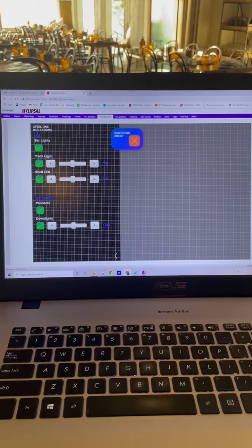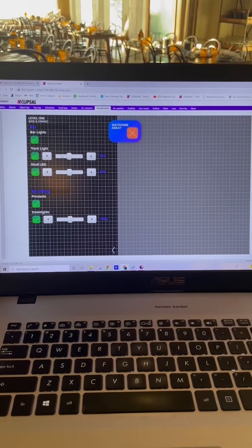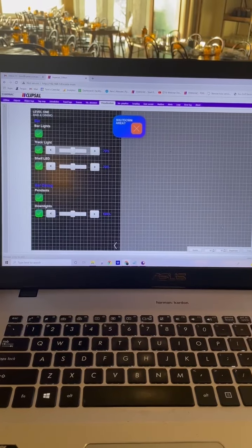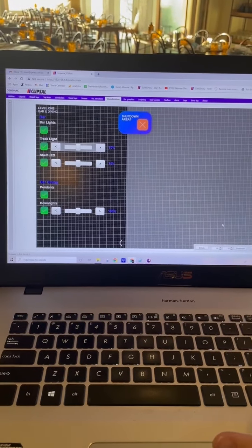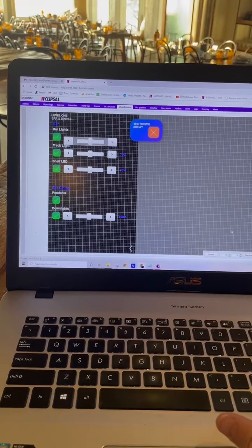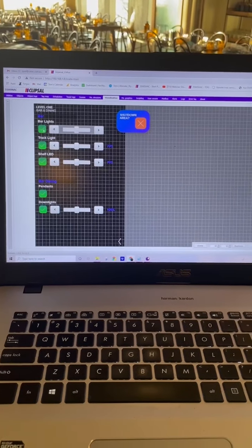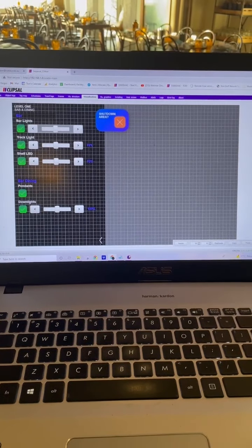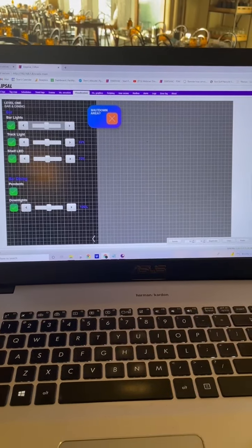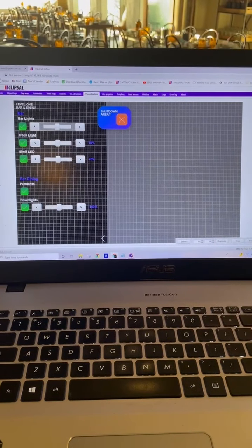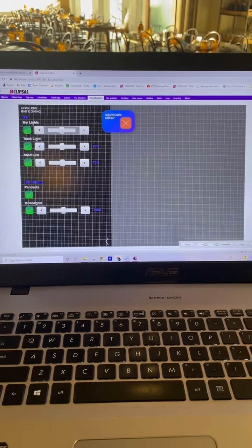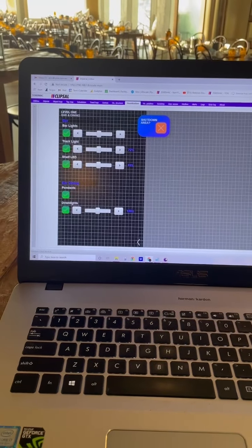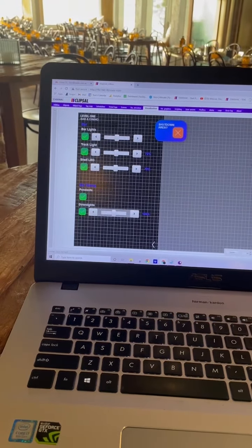Okay, now what I need to do is add some sliders in for the customer. So this is a light that has a slider, so if I just simply copy and paste that, I get that one in line. Click on this button here, see what that group address is, it's 60. Drop this one down and just type in 60. Apply. Save and reload, I'll do the same one here.